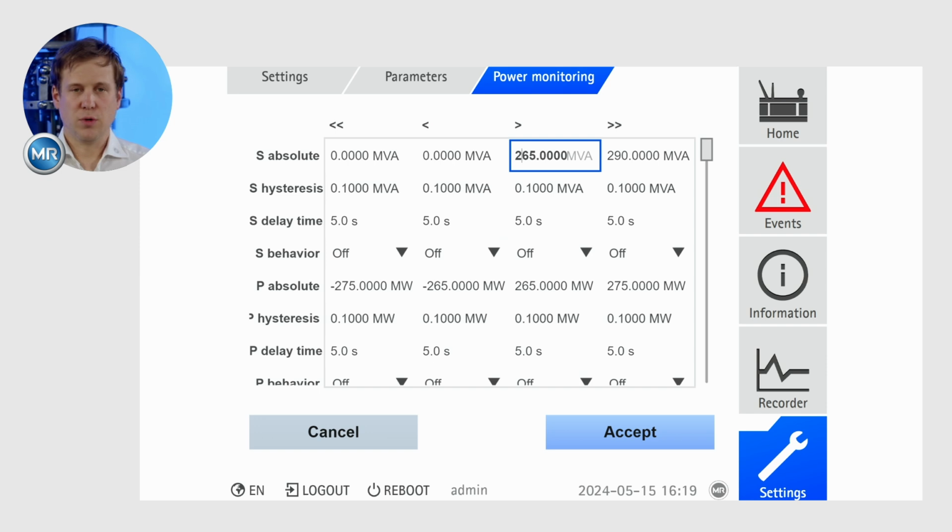Therefore, the expert mode can be easily used to speed up your commissioning. Be aware, if you make faults in the configuration, the system will simply say there are still errors on that page. But it will not tell you exactly where or what the problem is. If you're having trouble doing that, you can always go back, unselect the expert mode, and then you get, in the default mode, a much more complex explanation if you have a configurational error somewhere in the system.